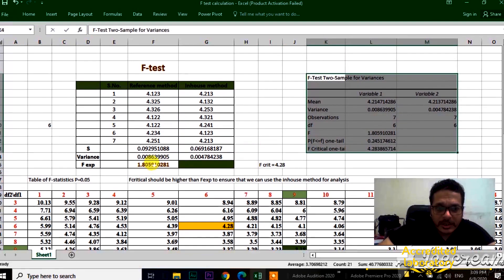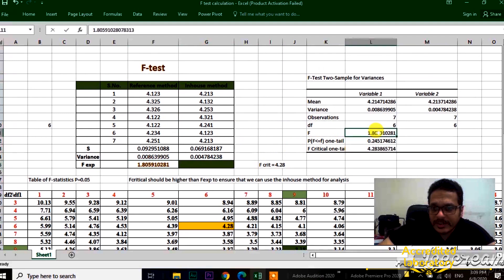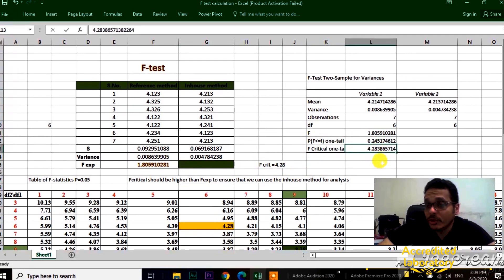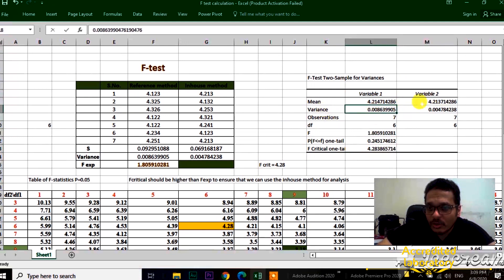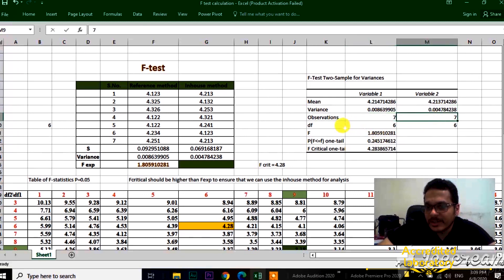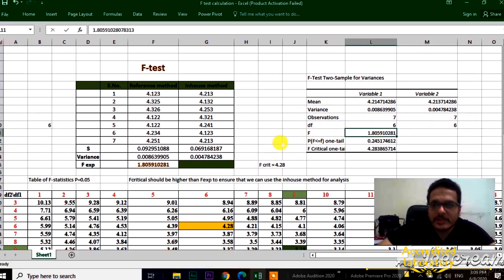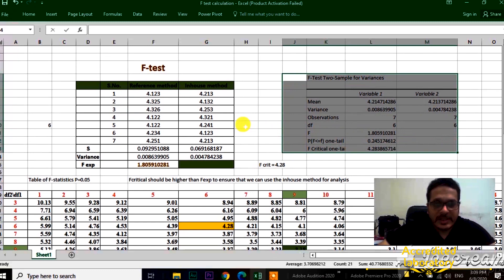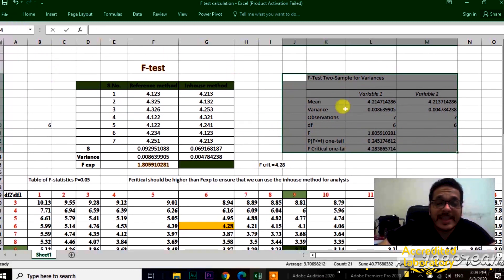Select the results for group one (reference method) and the results from the lab-developed method. For alpha — the level of significance — set it to 0.05, meaning the risk of accepted items being outside the limit is less than or equal to 5%, and likewise for rejected items. Select the output range for the results and click OK. The output table shows F-experimental = 1.8 and F-critical = 4.28, along with the mean for each group, the variance for each group, the number of observations, and the degrees of freedom — confirming the manual calculation.